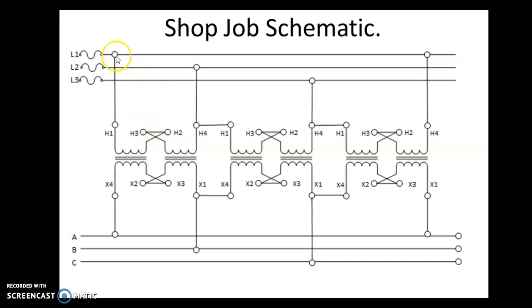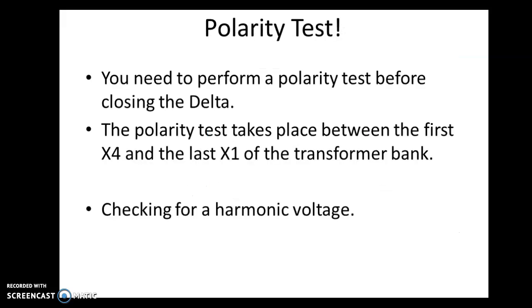On the primary side, the delta is closed by line 1 being connected to H1 as well as H4. On the secondary side, the delta is being closed between X4 and X1. Because we are generating power in a way, or inducing voltage onto the secondary side, there is a chance that the polarity could be incorrect and that we could be producing a very, very high voltage that is dangerous to the transformer as well as the electrician working on it. So what we want to do here is a polarity test. You need to perform a polarity test before closing the delta.